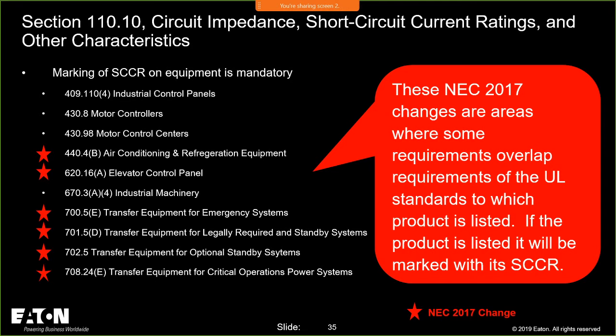So 408.6 probably should be added to this, because it says switchboards, switchgear, and panel boards shall have a short circuit current rating not less than the available fault current. In other than one and two family dwelling units, the available fault current, okay, no. 408.6 does not require that the panel board, switchboard, or switchgear be marked with the short circuit current rating. Interesting. No, it doesn't require. Okay, so I don't have to update this slide. But we're going to talk a little bit more about that anyway. And that could be a good public input, because every other area says you have to mark it, you have to mark it with the short circuit current rating, and this discussion needs to be had. I'll explain why it's a little more complicated with those types of equipment.